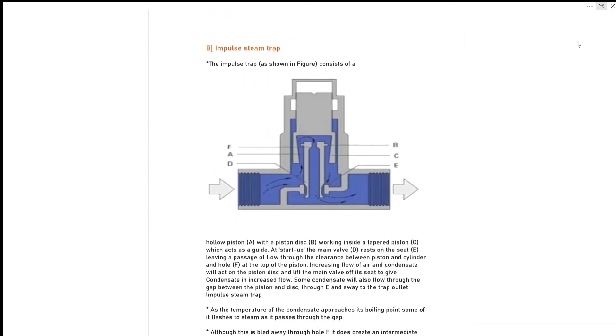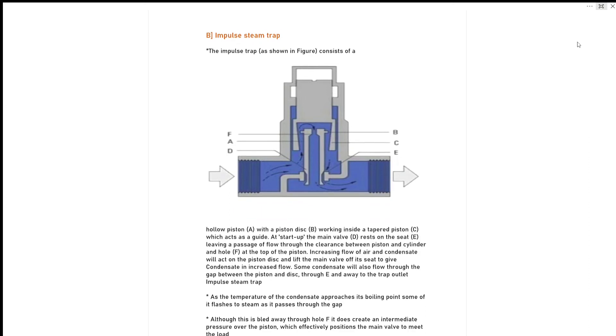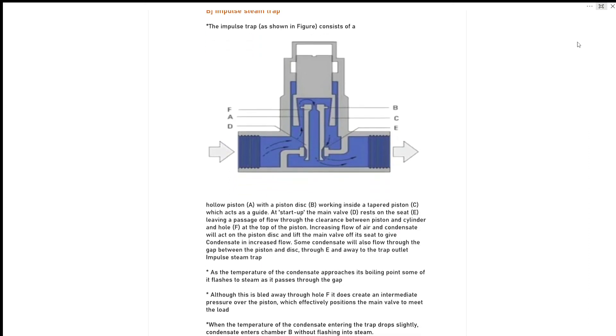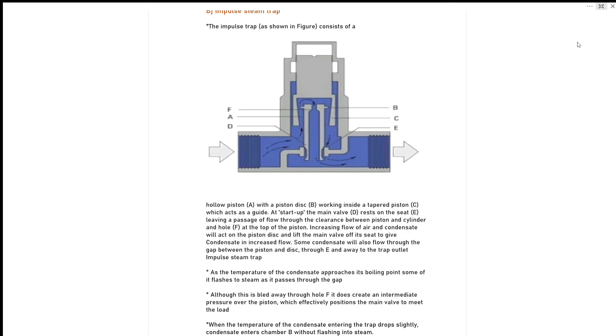Second type in thermodynamic steam trap is impulse steam trap. Impulse steam trap figure is shown below - you can see the figure and the naming is given here A, B, C, D. Hollow piston A with a piston disc B working inside the tapered piston C which acts as a guide. At startup, the main valve D rests on the seat, leaving a passage of flow through the clearance between piston and cylinder and hole F at the top of the piston, increasing flow of air and condensate.